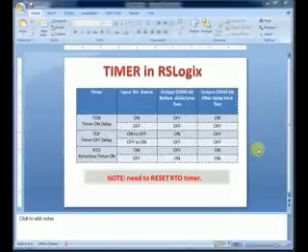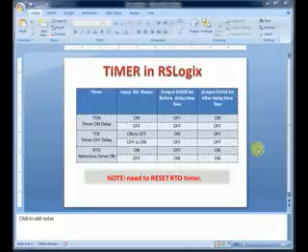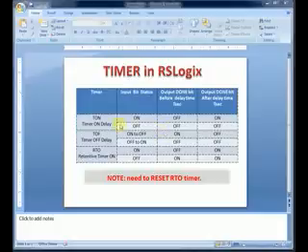Let's see timers in RSLogix. The basic work of a timer is to generate a delay into your program, and the delay will be as per the programmer. Into RSLogix, there are three types of timers: TON, TOFF, and RTON - timer on delay, timer off delay, and retentive timer.